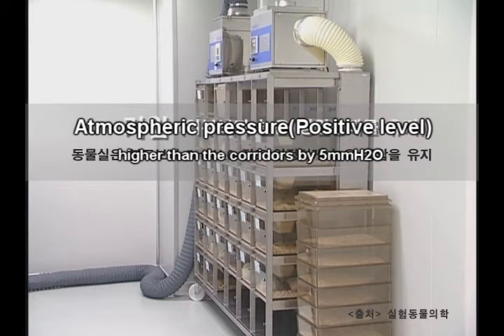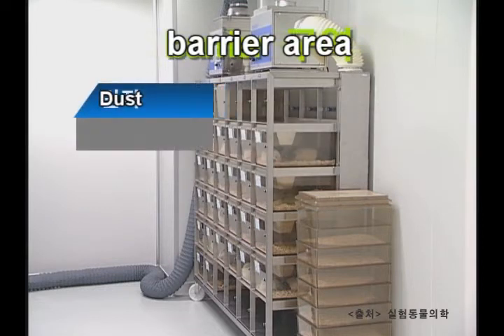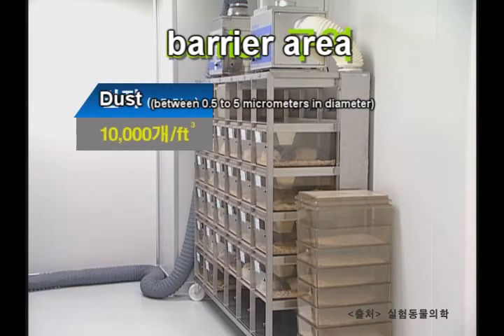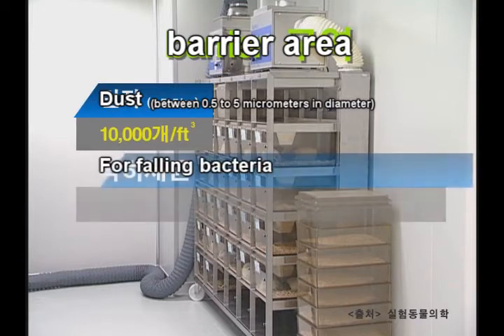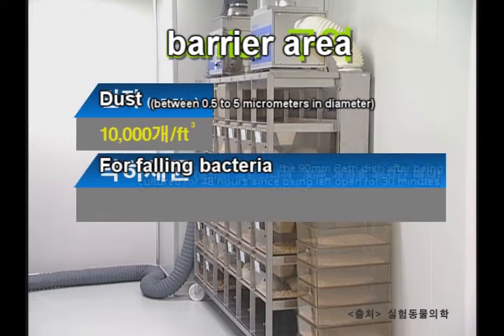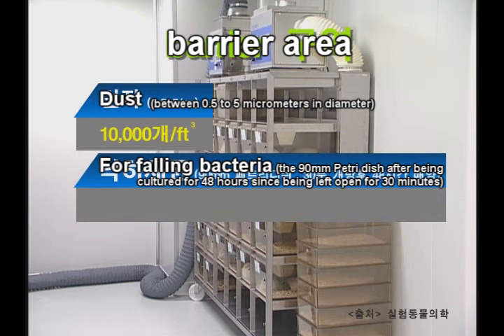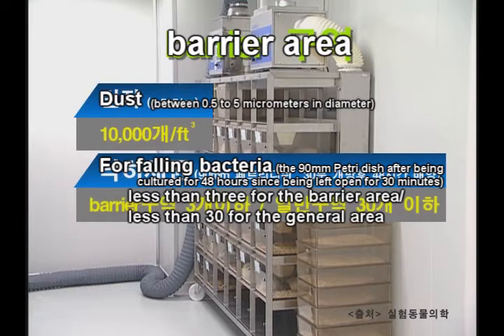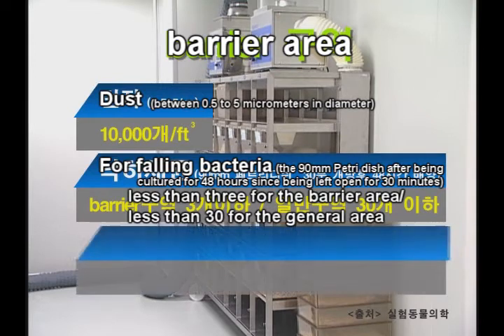For the barrier area, when an animal is not occupying it, there must be less than 10,000 molecules of dust per feet squared that are between 0.5 to 5 micrometers in diameter. For falling bacteria, the 90 millimeter Petri dish with blood agar medium, after being cultured for 48 hours since being left open for 30 minutes, there must be less than 3 for the barrier area with no animal present, and less than 30 for the general area. For odor, the ammonia concentration should not exceed 20 ppm in the barrier area where the animals are bred.